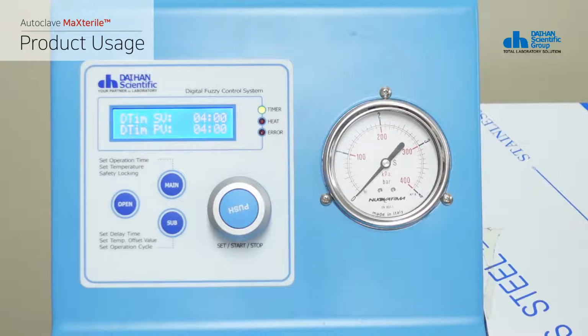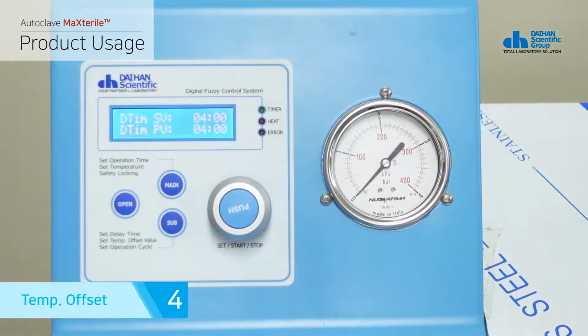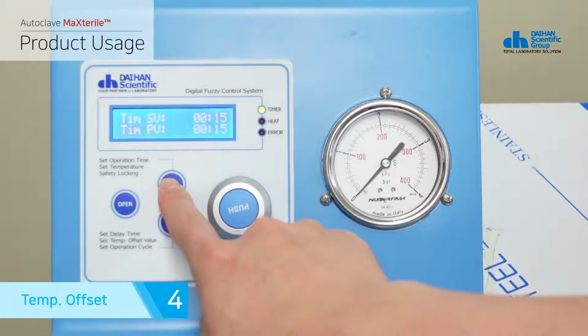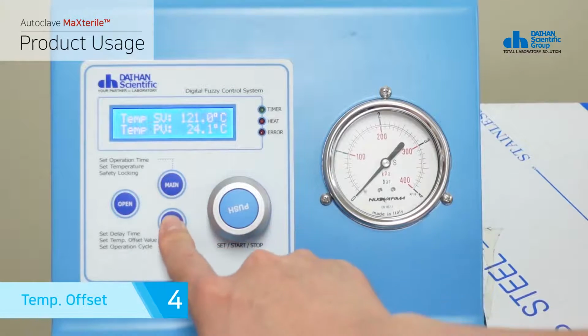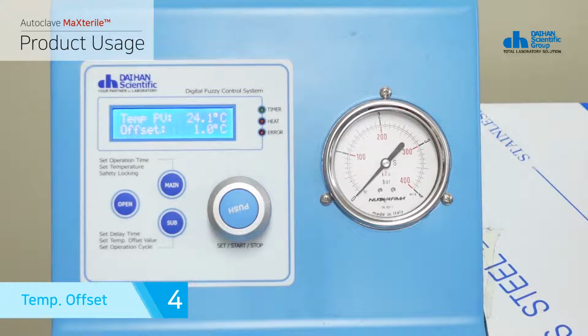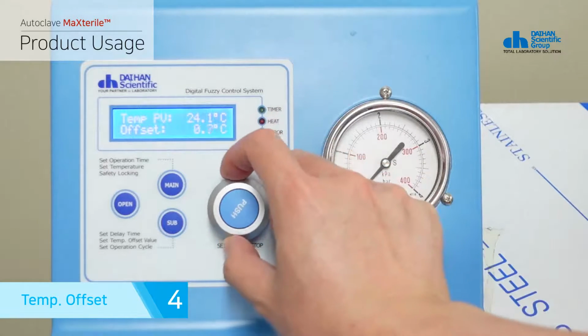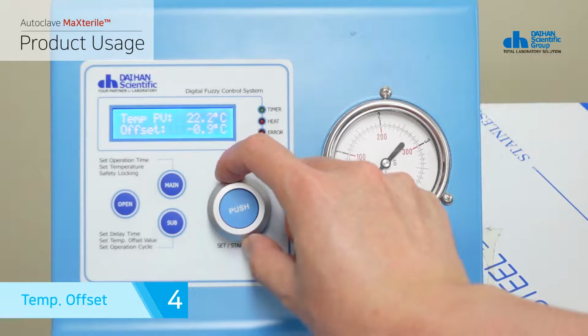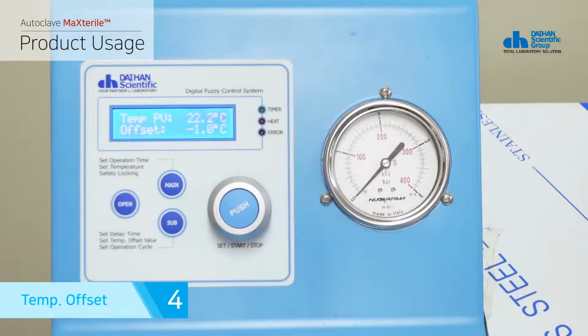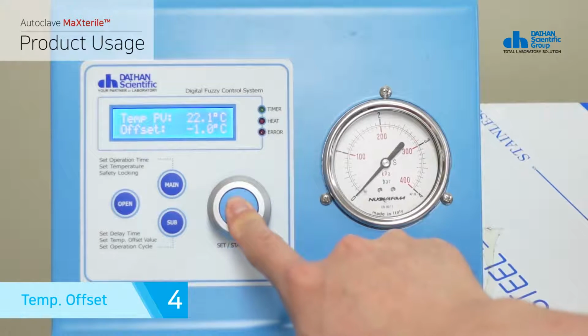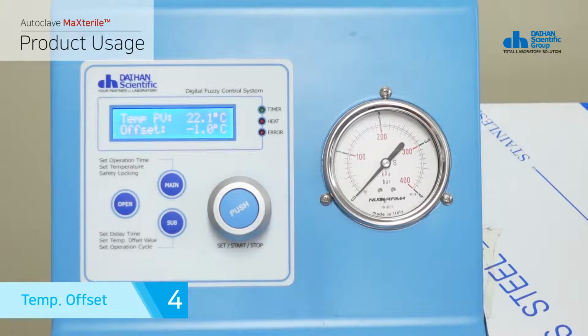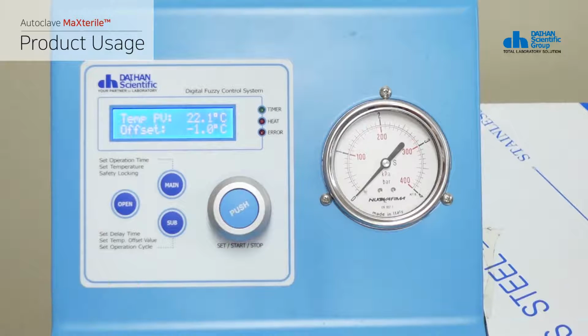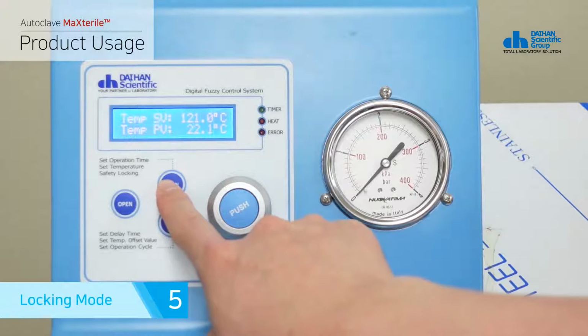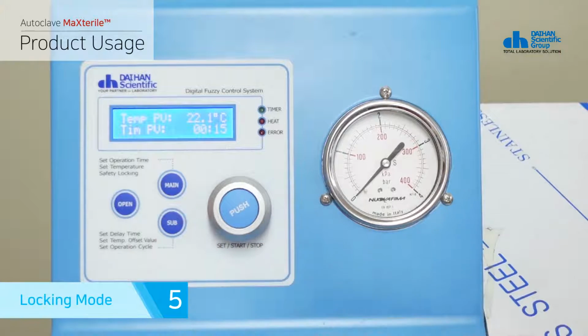If you press the sub button on the operation temperature setting screen, it switches to the settings screen. We use this to match the current temperature of the product with the thermometer. Being used as the basis for our experiment, it can be adjusted in 0.1 degree increments in the range of -10 degrees to +10 degrees, and the offset value is saved by pressing jog dial for 2 seconds. If you press the main button on the operation temperature settings screen, it switches to the lock mode.